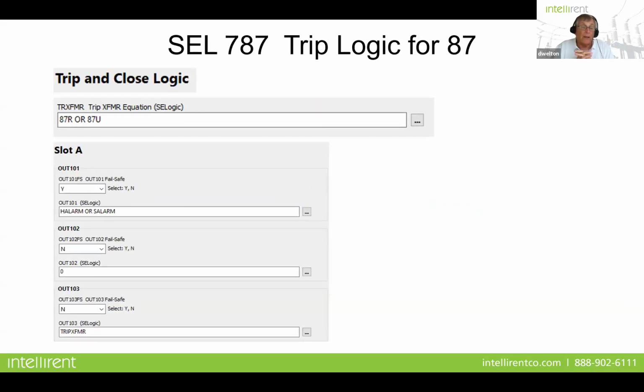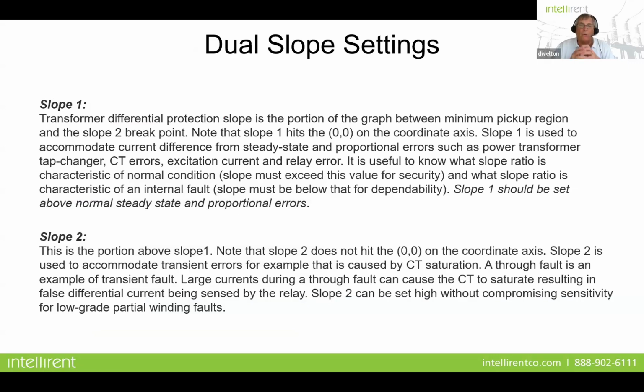Trip logic is very, very important, especially with the Schweitzer. Now, with the Beckwith, it was easy. We just checked a box. It said, go to output 1. With a Schweitzer, you have to say it's going out to a certain protective function, but it has to be part of the trip logic equation. And this can be a little bit complex. You can actually enable the element, but forget to output it to a contact, whether it's an alarm, or an alarm and a trip, or just a trip. So it's important to make sure that these are done properly.